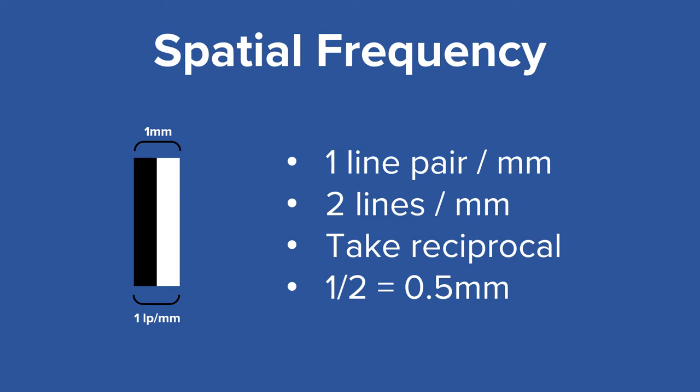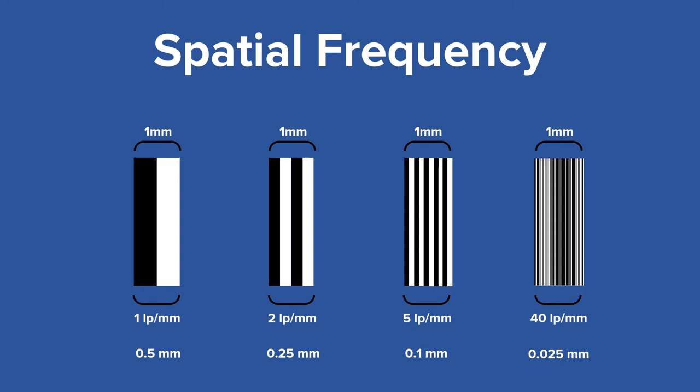Spatial frequency is a measure of how small you can see an individual object. For example, if we have one line pair per millimeter, we're actually seeing two lines per millimeter. If you take the reciprocal of that, you're actually being able to see an individual object that is 0.5 millimeters. At one line pair per millimeter, you can distinguish an object that is 0.5 millimeters in length.